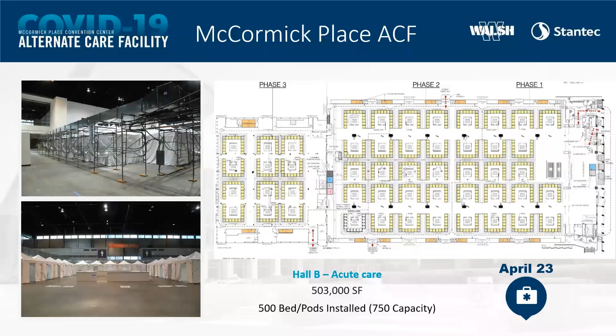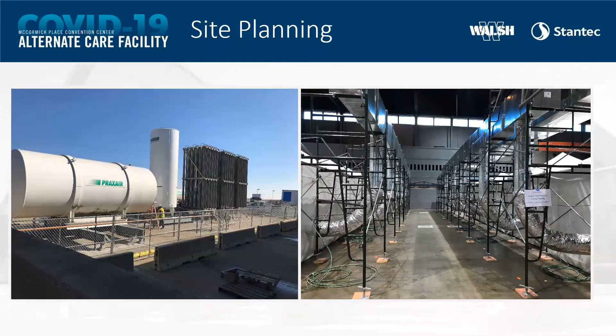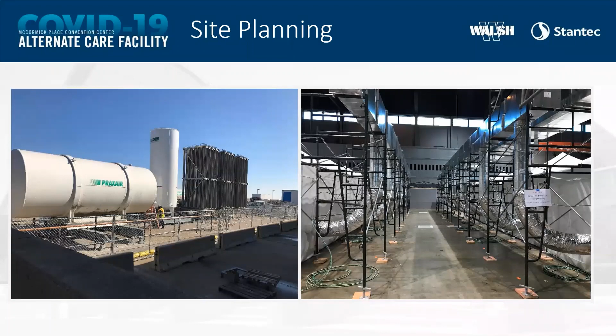All of this was done using modular and prefab, most of which was done off-site, trucked to the facility, and simply put together. Next slide. The picture on the left here is our medical oxygen tank farm, which is located off the loading dock outside of the McCormick Place facility. On the right is the infrastructure and scaffolding that we put together to accept all of the medium pressure duct, the copper pipe for the oxygen lines, and the vacuum, all of our emergency power. So really the bones that accepted all of the mechanical, electrical, and plumbing systems. Next slide.